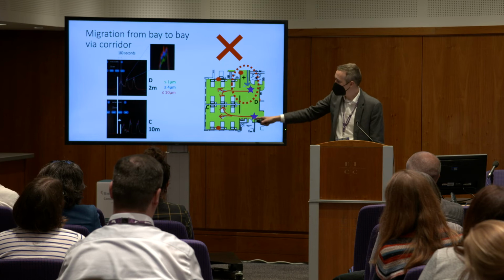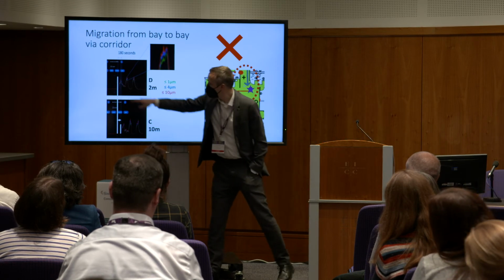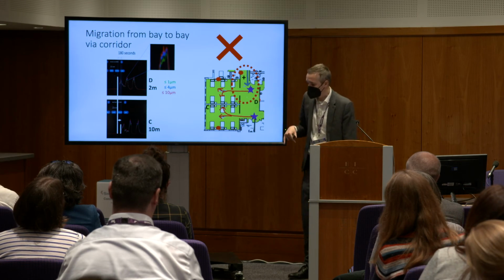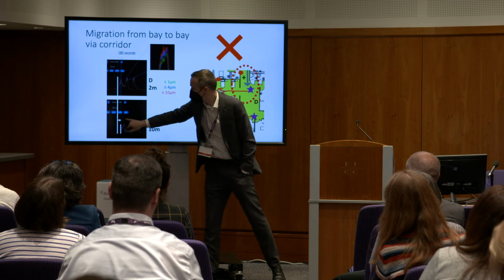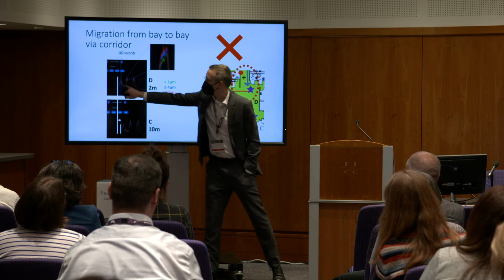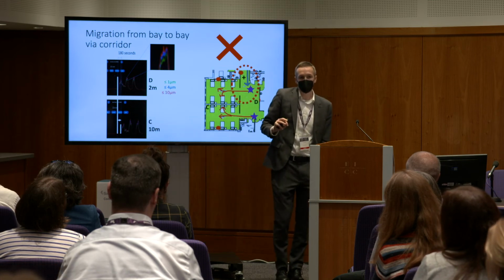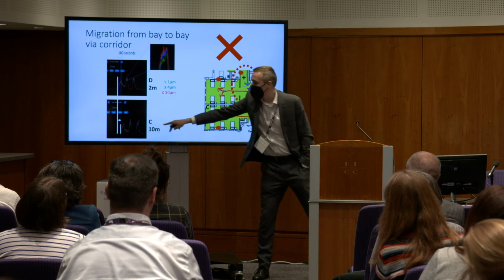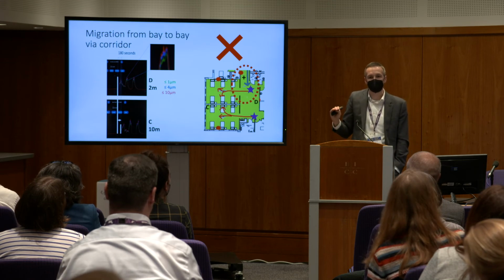So what we saw is when we actually let off the nebulizers, you get a spike here at sensor D, which is here, and then about 3 minutes later, well exactly 3 minutes later, 180 seconds, you get the same spike. And you can't say that is not the same as that. Bearing in mind, these sensors don't talk to each other, they just report to a central unit. So that is mirroring. And what's equally unfortunate is that it's mirroring it in exactly the same quantity.